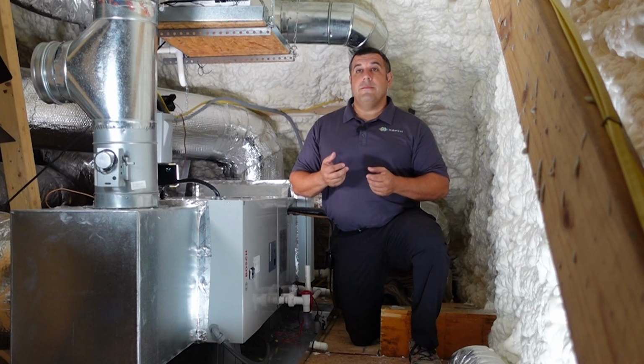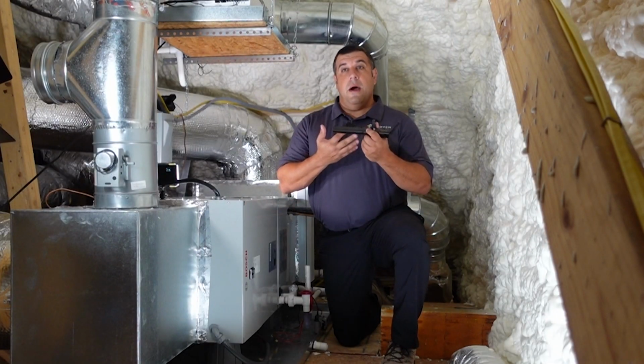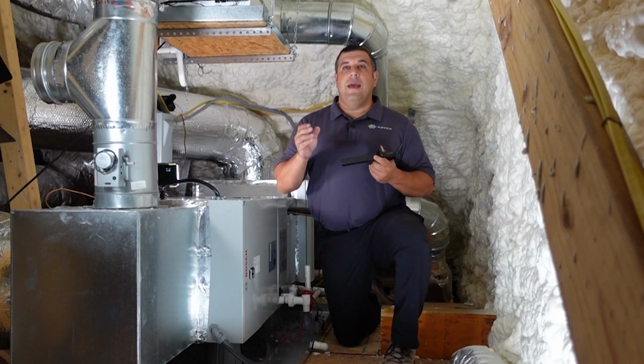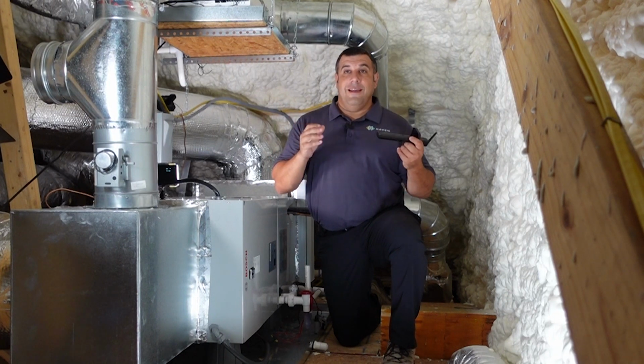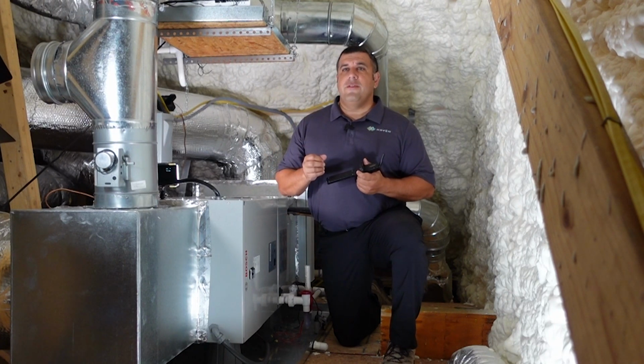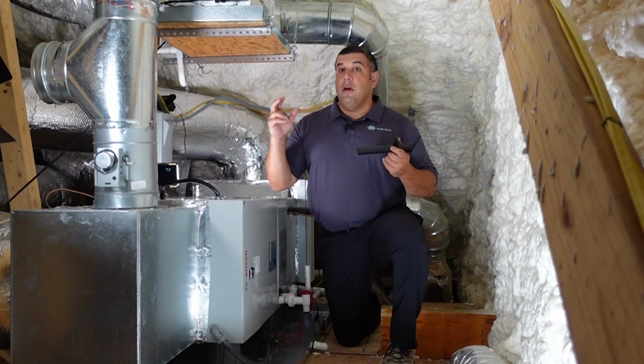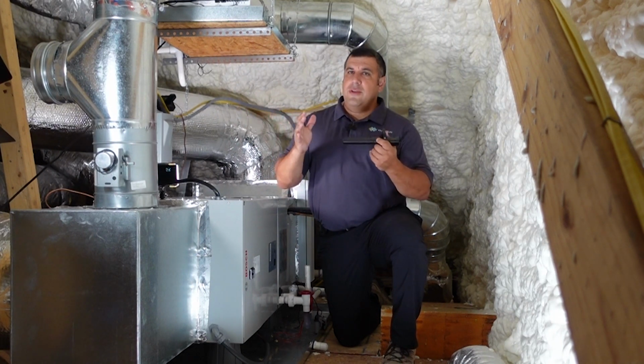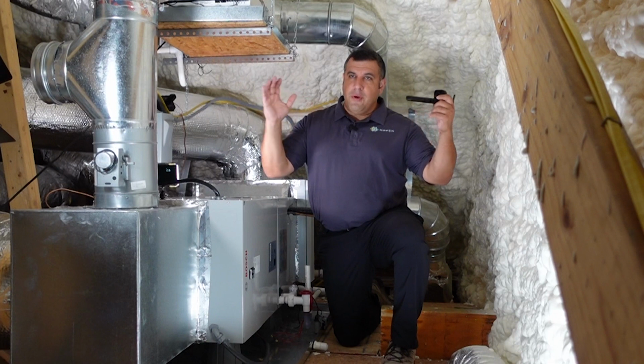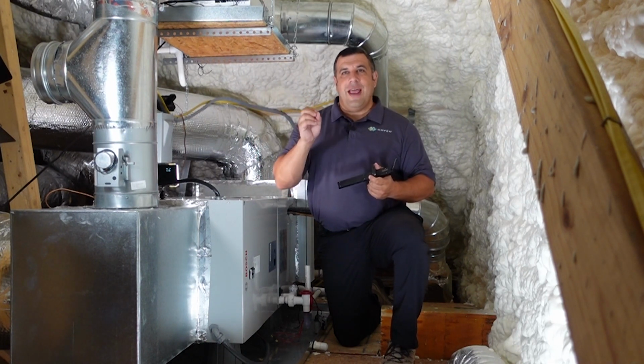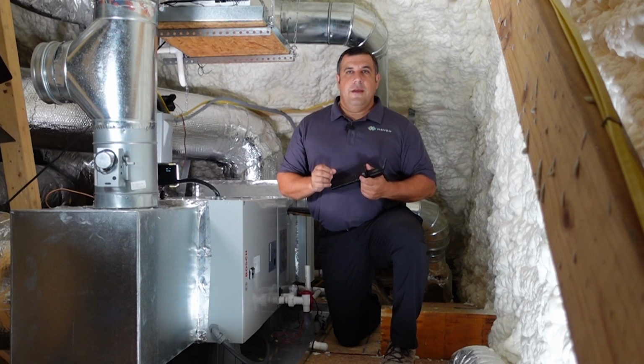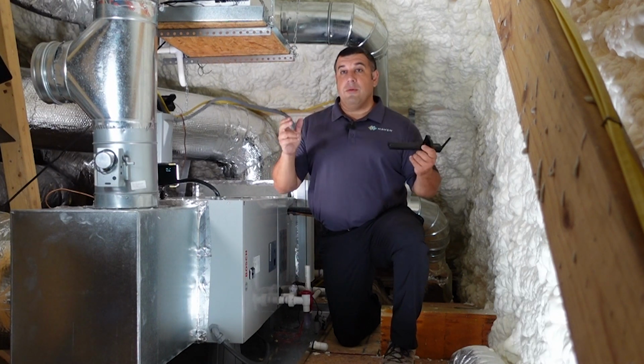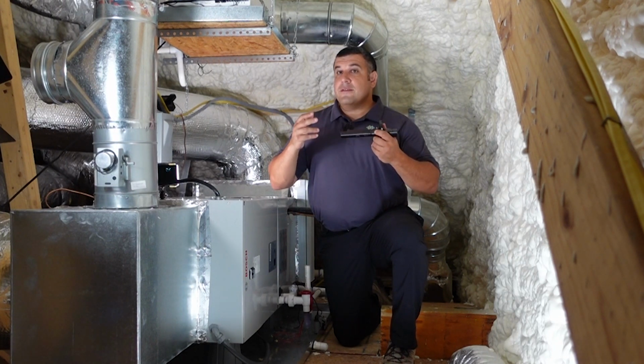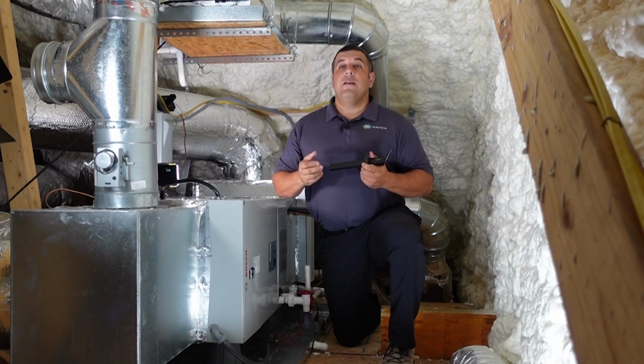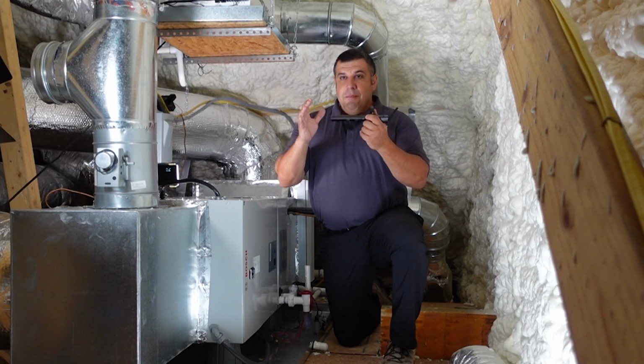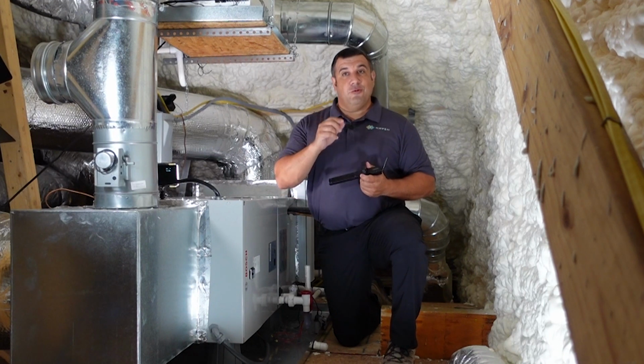Make sure that the monitor is installed at least 12 inches away from duct bends or obstructions like filters, and ideally 24 inches is best. These obstructions can cause turbulence in the airflow, which can reduce the accuracy of the sensors. A straight piece of ductwork is always recommended to establish a stable airflow signal. The best case scenario is on rigid metal duct, but the monitor can also be installed on ductboard and flex duct. For best results, adding a rigid metal section or collar on flex duct is recommended.